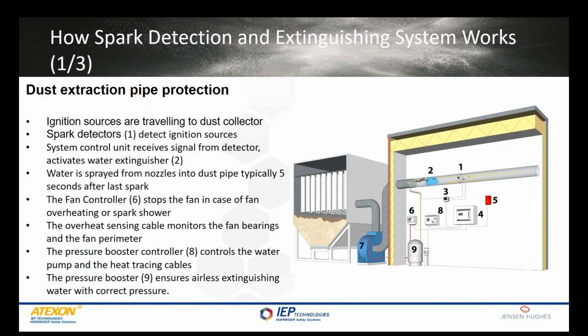The fan controller, number 6, stops the fan in case of fan overheating or spark shower. Typical limit for spark shower is 3 sparks within 6 seconds. The function of pressure booster station numbers 8 and 9 is to provide airless extinguishing water with sufficient water pressure level so that optimized water droplet size and extinguishing response time can be achieved. Pressure booster controller also takes care of pipe and extinguisher heating in case of outdoor installation.